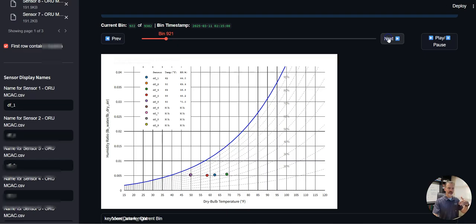and then as the weather starts warming up, I think we have some warm up pretty soon here. You can see that, okay, it starts warming up here, but you notice all of a sudden the sensor in the interstitial space above insulation but below deck is now getting hot, so it's being vaporized, right? And so it's actually tracking up the psychrometric curve, so you can tell the insulation is saturated at that point because outside air is not following it.